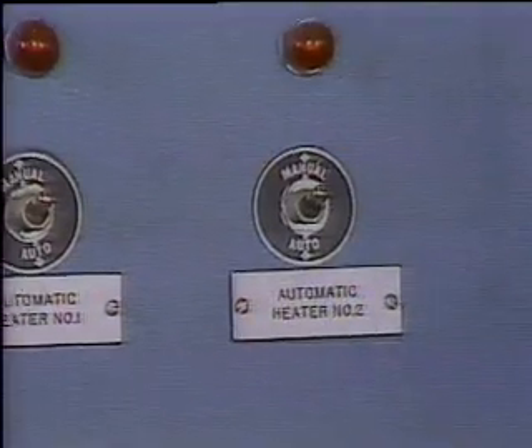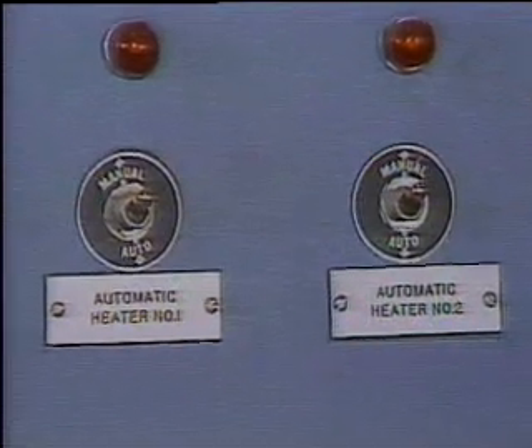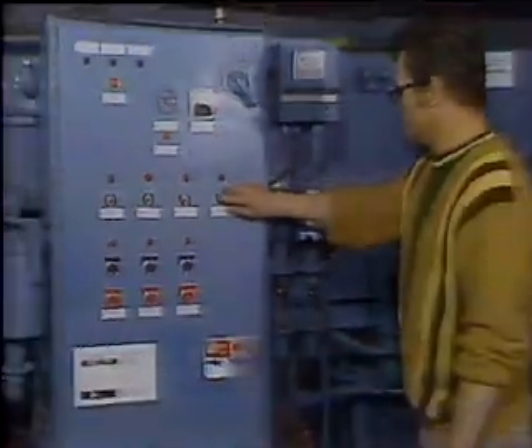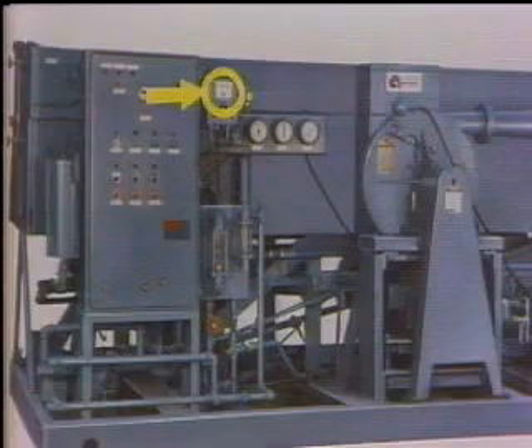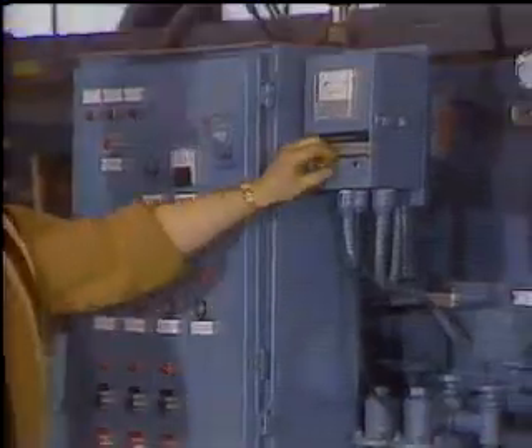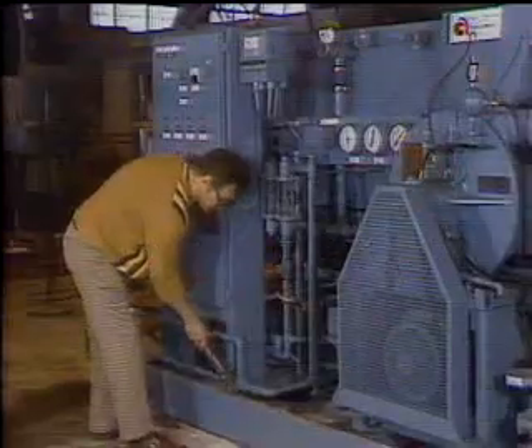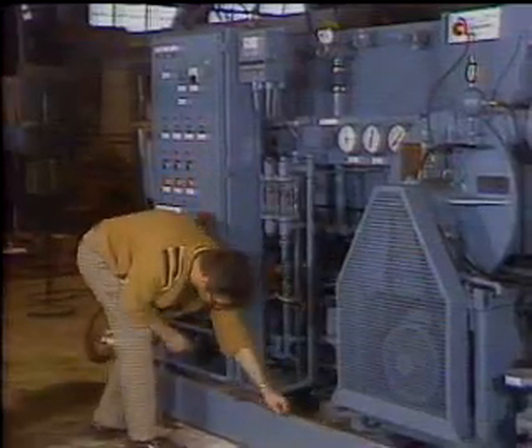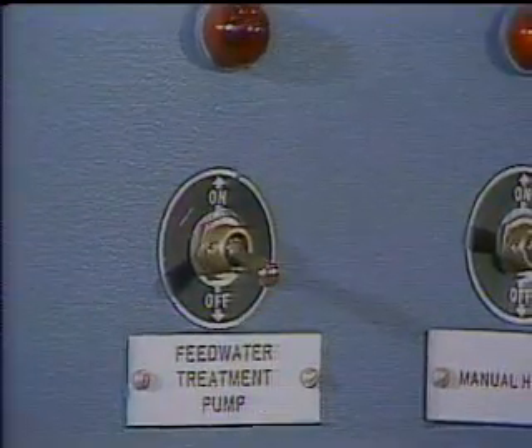When everything seems to be flowing smoothly, turn the automatic heaters to auto. One manual heater should be on. Next, turn the salinity meter on. If the distillate is pure, the meter will read 5 parts per million or less. Once it gets to this stage, the distillate can be stored, and the chemical treatment pump can be turned on. Make sure that the chemical treatment tank is filled with the proper chemicals.